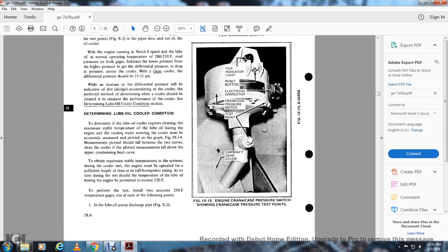Determining lube oil cooler condition: Determine if the lube oil cooler requires cleaning by measuring the maximum stable temperature of the lube oil leaving the engine versus the engine cooling water entering the cooler. These temperatures may be accurately measured and plotted on figure 9-14. Measurements shall fall between the two curves of the clean cooler region; if the plotted measurement falls above the upper condemning limit curve, the cooler must be cleaned. To obtain valid measurements, the engine must be operated at full horsepower rating for a sufficient length of time. At no time during the test should the lube oil temperature leaving the engine be permitted to exceed 220°F.